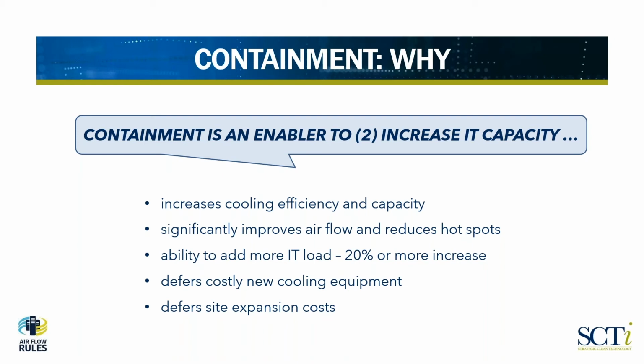So what does all that mean? It means you can now defer the costs for new cooling equipment. If you were having hotspots and you thought you would have to put more cooling equipment in place, with containment, which is much more cost effective and doesn't have an ongoing energy cost associated with it, you can defer that purchase of new cooling equipment. And you can also defer site expansion in most cases, because now you can load your racks up to a higher density than you could previously.